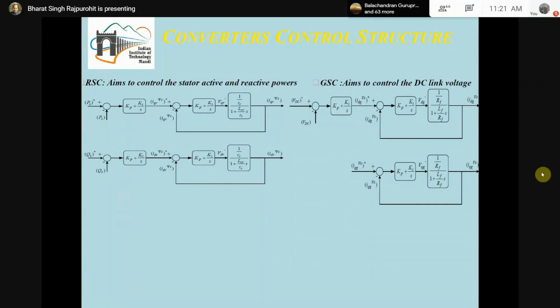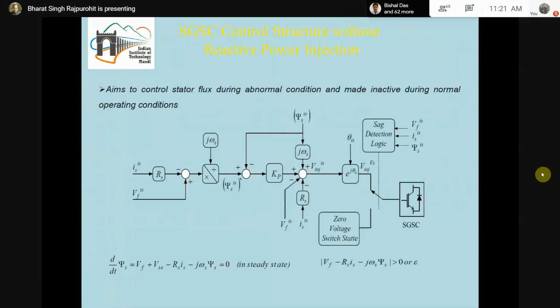If the static compensator role is required, then we need to provide this loop also to provide the reactive power from the grid side converter or line side converter. So that is also possible. This is a logic diagram for the series grid side converter. Below, the logic is given. Whenever this logic is fulfilled, the series grid side converter comes into the picture. Otherwise it is in idle condition, and it will be able to provide the required reactive power as well as the required compensation into the series.